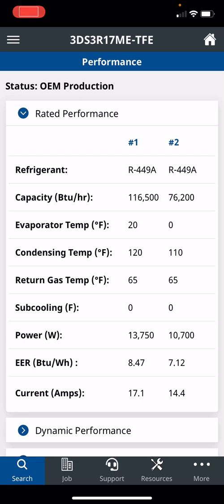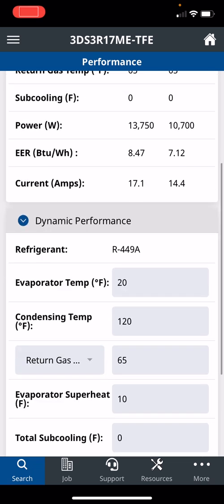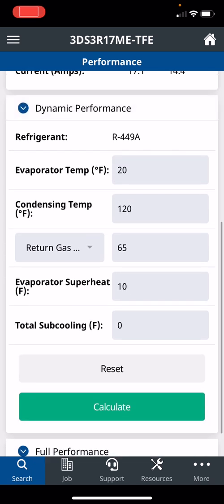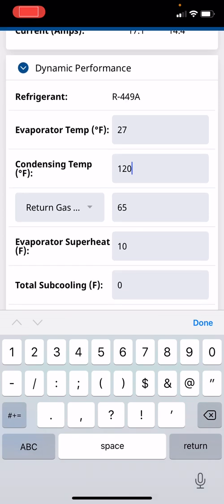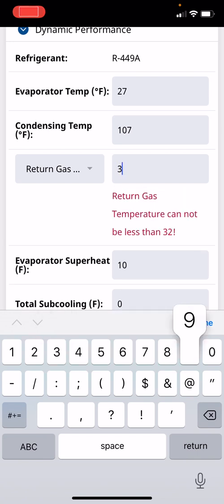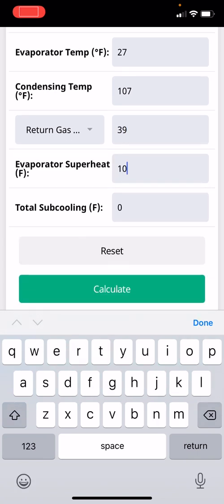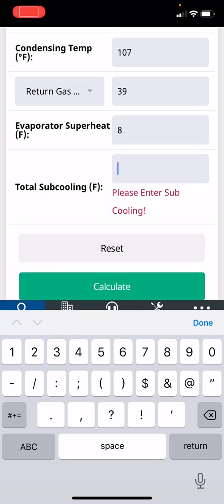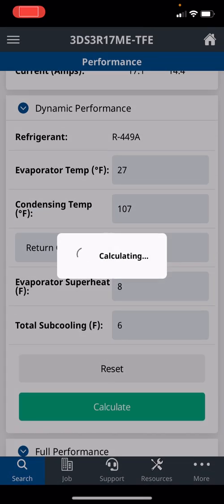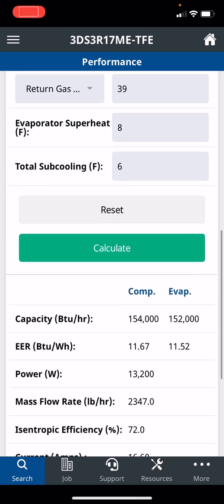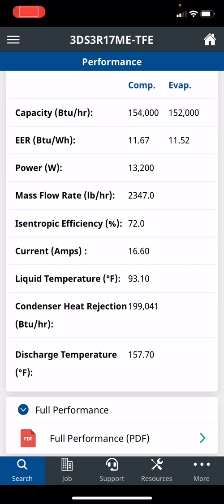Not very important to you as a technician, but if you go into dynamic performance now and you know this is running at 27 evaporator temperature, you're running at 107 condensing temperature, your return gas is 39, you know your superheat is 8, and your subcooling is 6, you calculate. These are the conditions this compressor is running in.